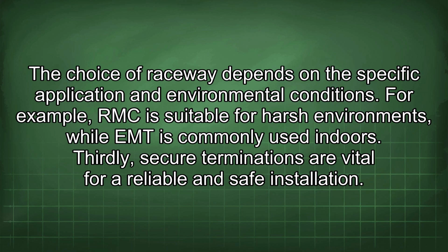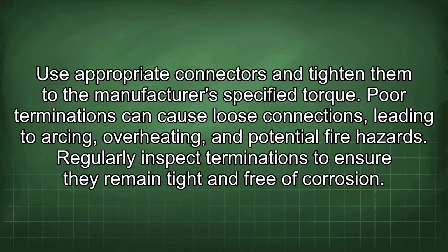Thirdly, secure terminations are vital for a reliable and safe installation. Use appropriate connectors and tighten them to the manufacturer's specified torque. Poor terminations can cause loose connections, leading to arcing, overheating, and potential fire hazards. Regularly inspect terminations to ensure they remain tight and free of corrosion.